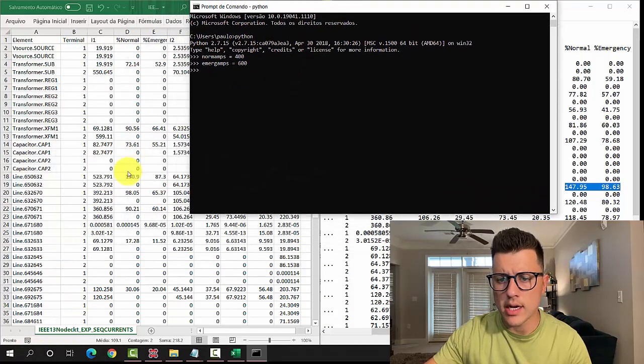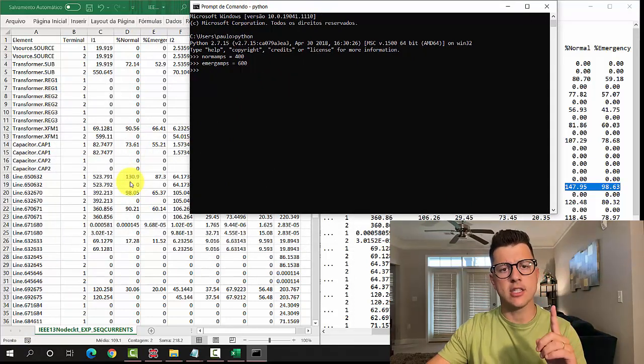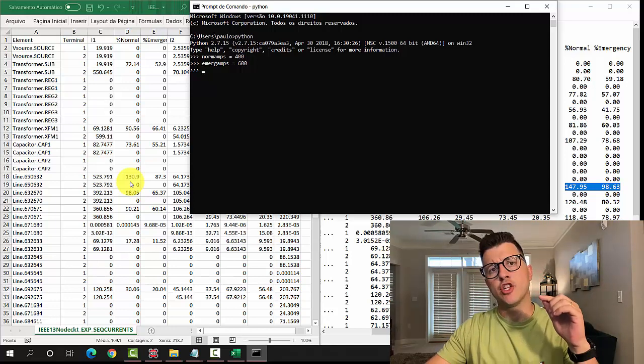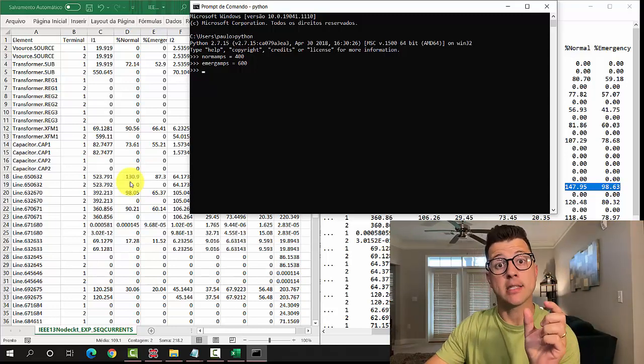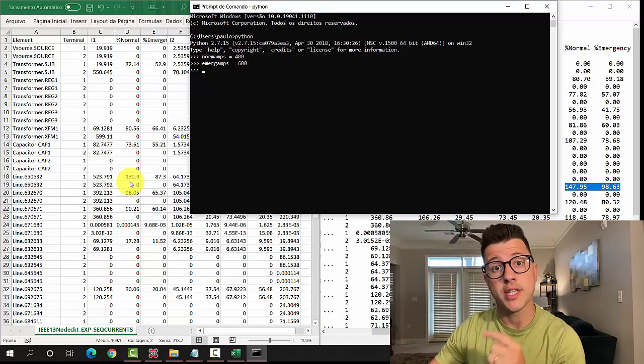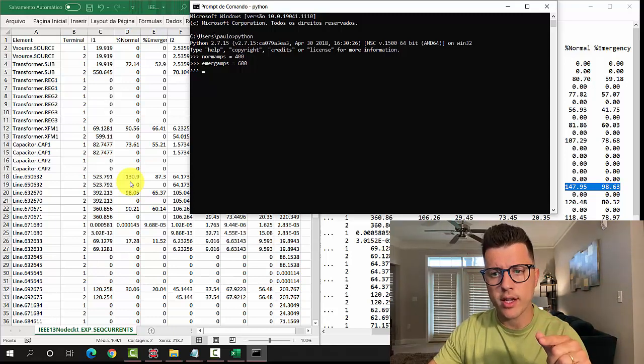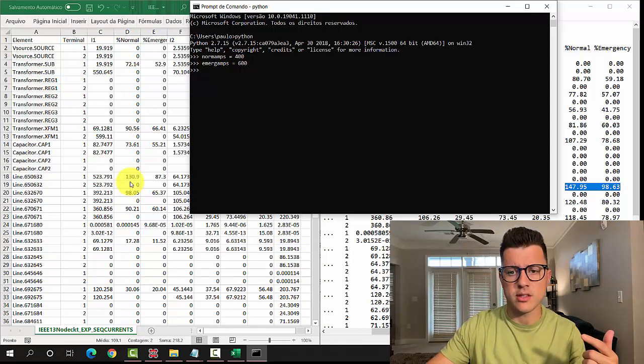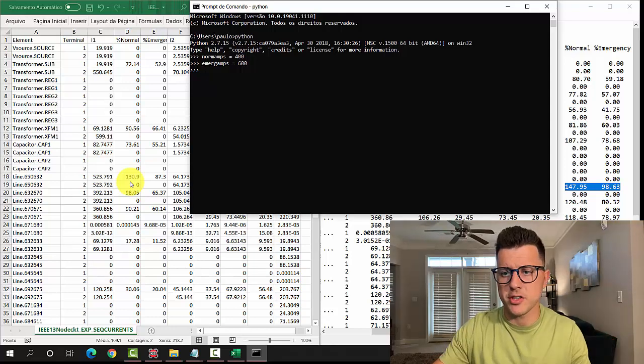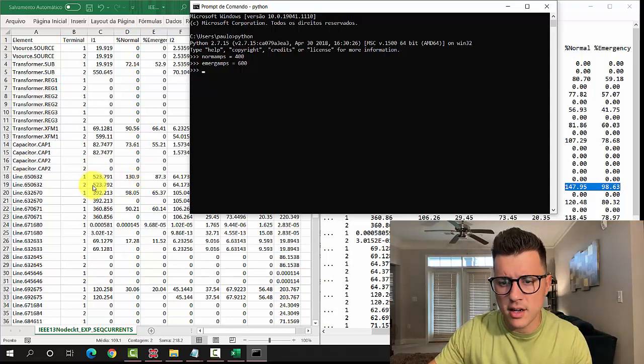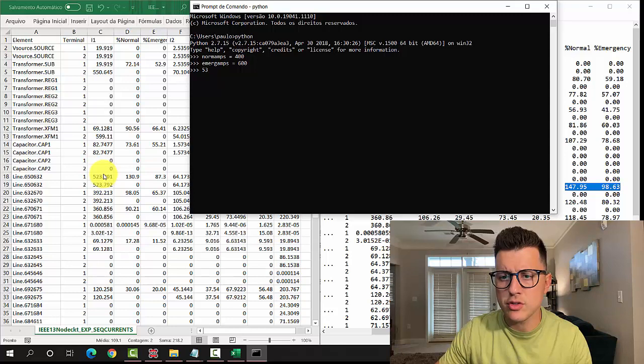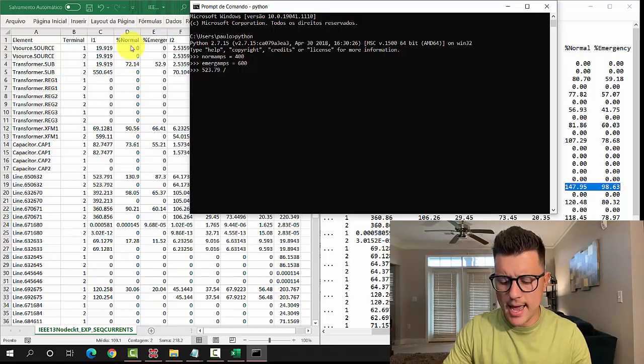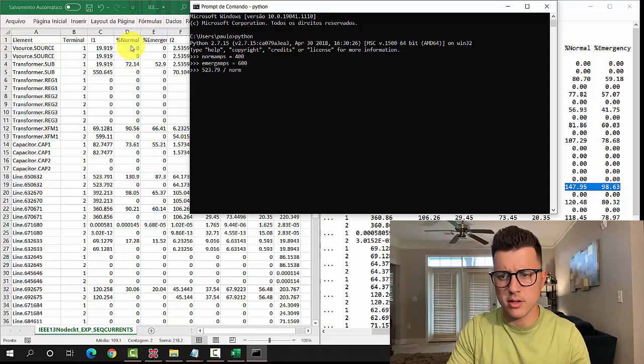To get this 130.9, what OpenDSS is doing is not going to the phase currents and getting the maximum for the terminal as we did in the previous video. It's actually now going to the positive sequence component of this terminal, which is 523.79, and dividing by norm amps.